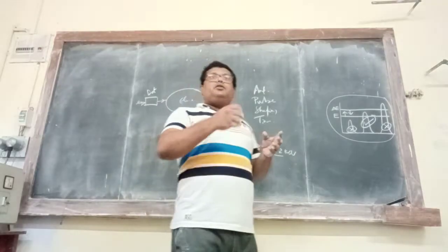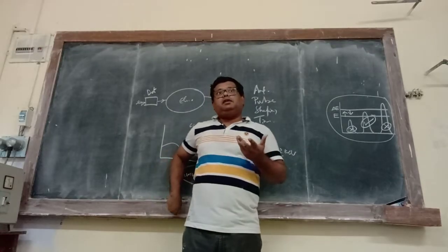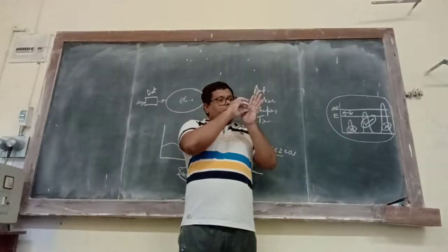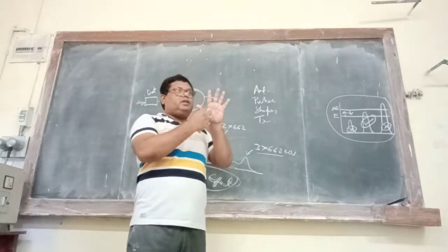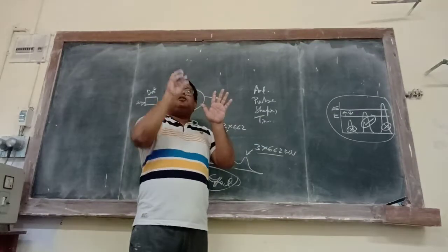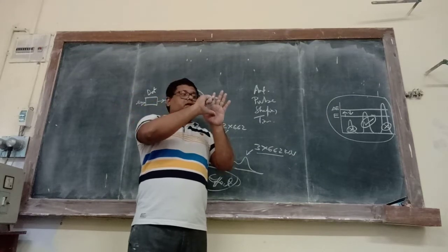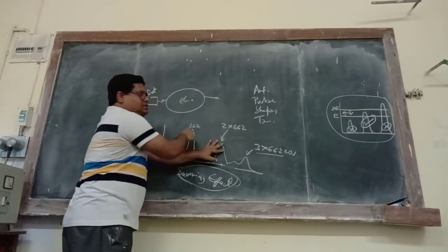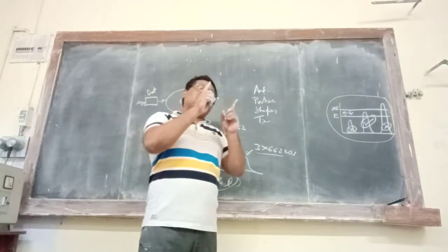To get rid of the problem, there are 2 ways. Number 1, put the source a little bit far, or use a segmented type of detector. I mean, when the gamma rays are entering the detector, if you make a detector granular, with more and more smaller components, the possibility of 2 gamma rays entering a single detector decreases. If you have multiple smaller detectors, then at a time 2 gamma rays will enter 2 separate detectors, and you will get a single event. You will get this signal from 2 separate detectors. And no such summing effect will be observed in a single detector.